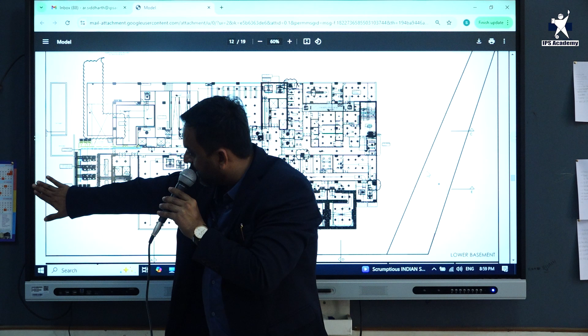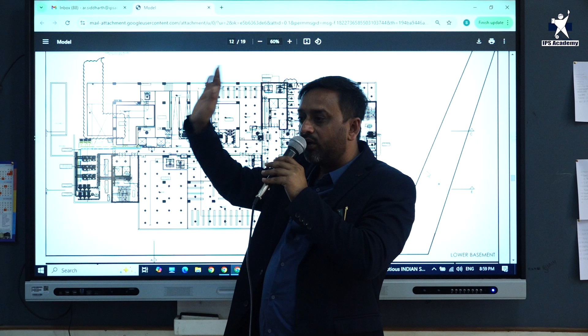From there, cables are going down to basement 2. And from there only every circulation, water supply from here, hot water supply from here, the rings are made at basement 1 or the service floor or the terrace. So all the cables are going like this, and we are having the appropriate shafts at each corner so that the cable lengths are not high. So the cables are moving vertically with the raceways. Actually we have not used cable, we have used BBT, bus bar trunking. Yeah. So to avoid the length or juggling of cables, because it is very easy to have one bus bar trunking and tap boxes to tap the local floor.